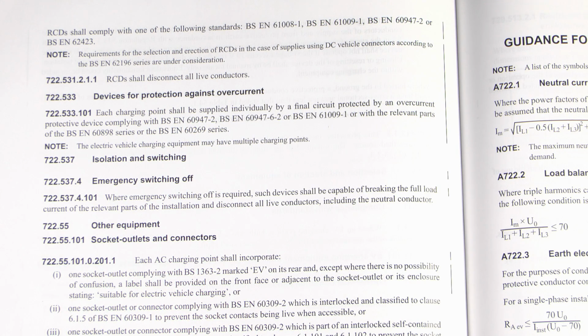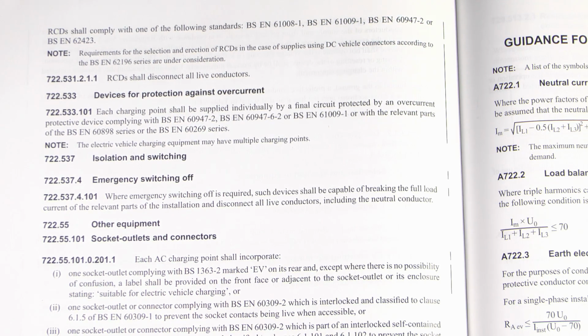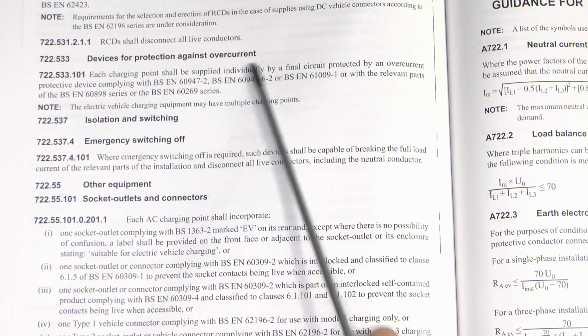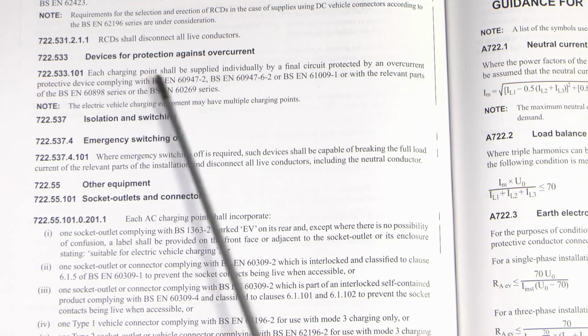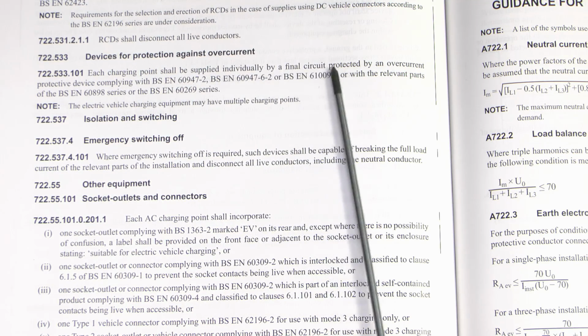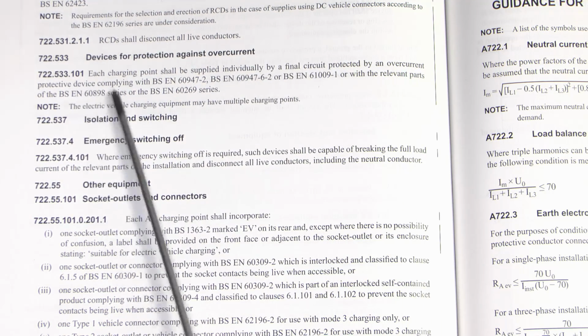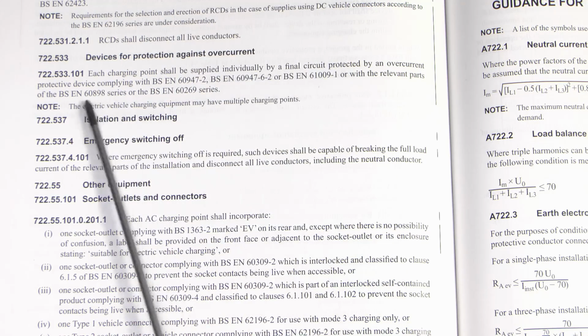It's not just the normal 30 milliamp type you would put in, say, a house for example. Devices for protection against overcurrent: each charging point shall be supplied individually by a final circuit protected by an overcurrent protective device complying with one of the choices here.